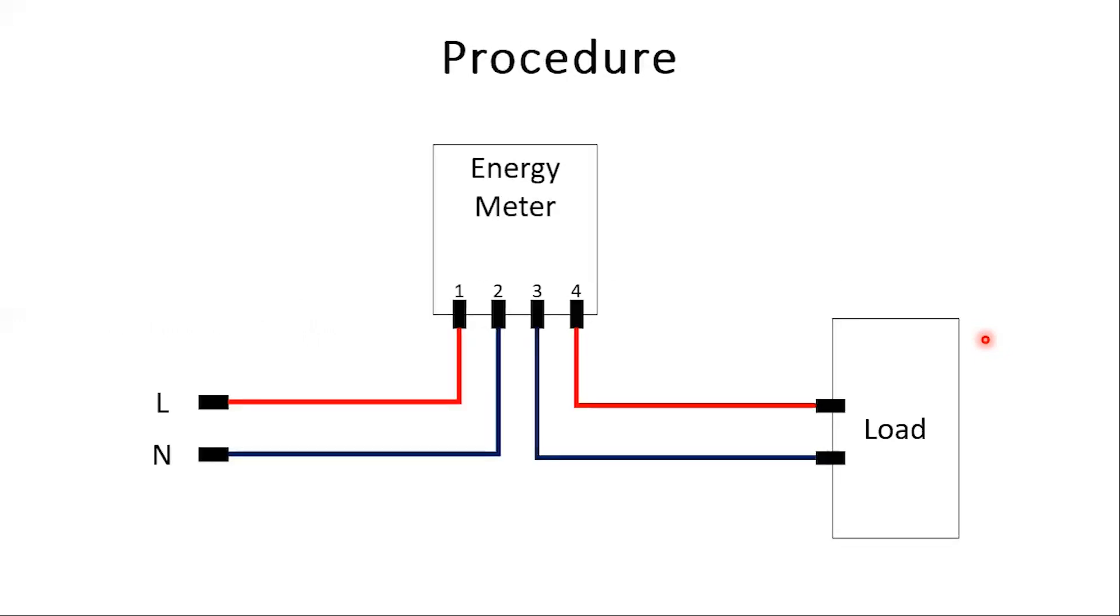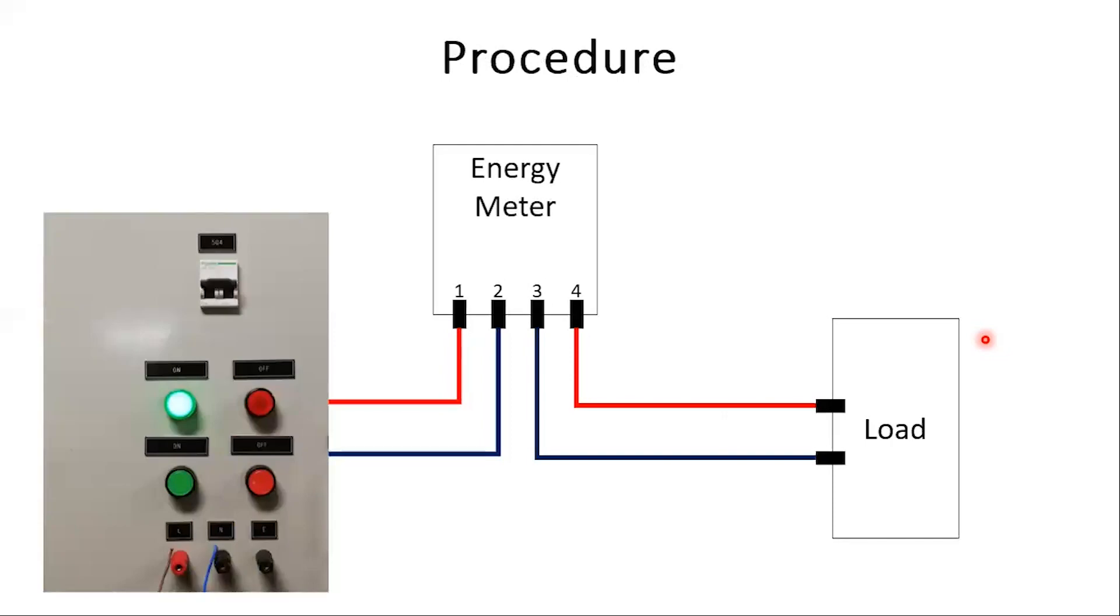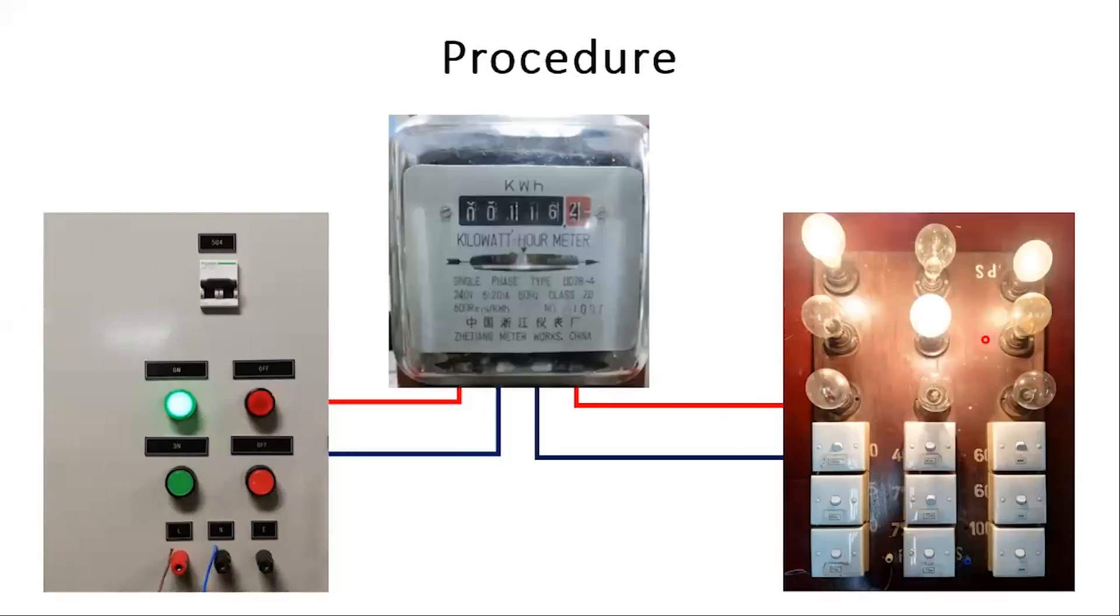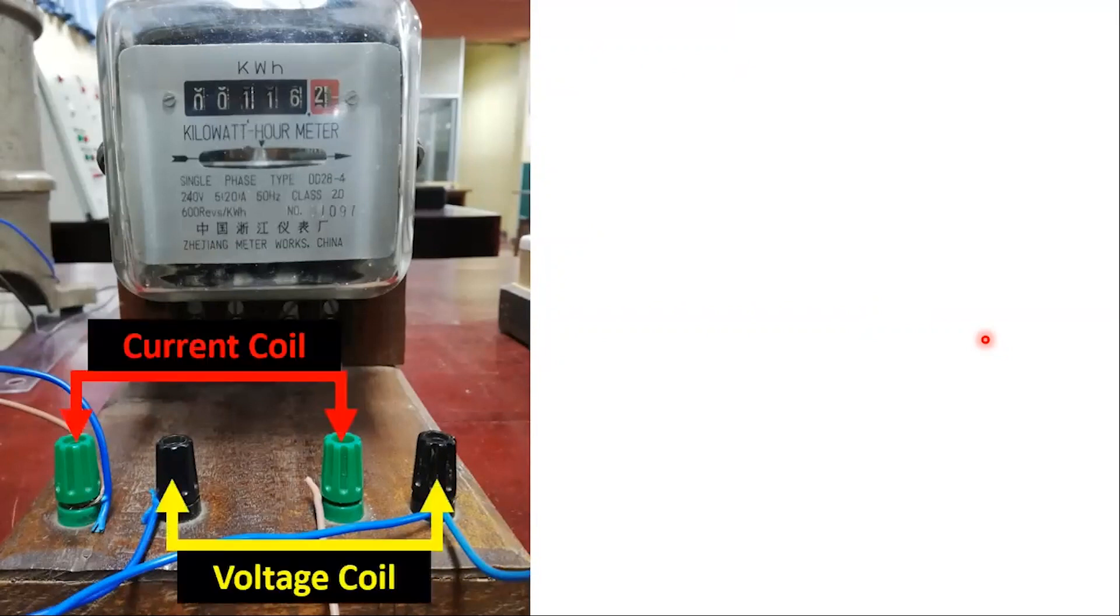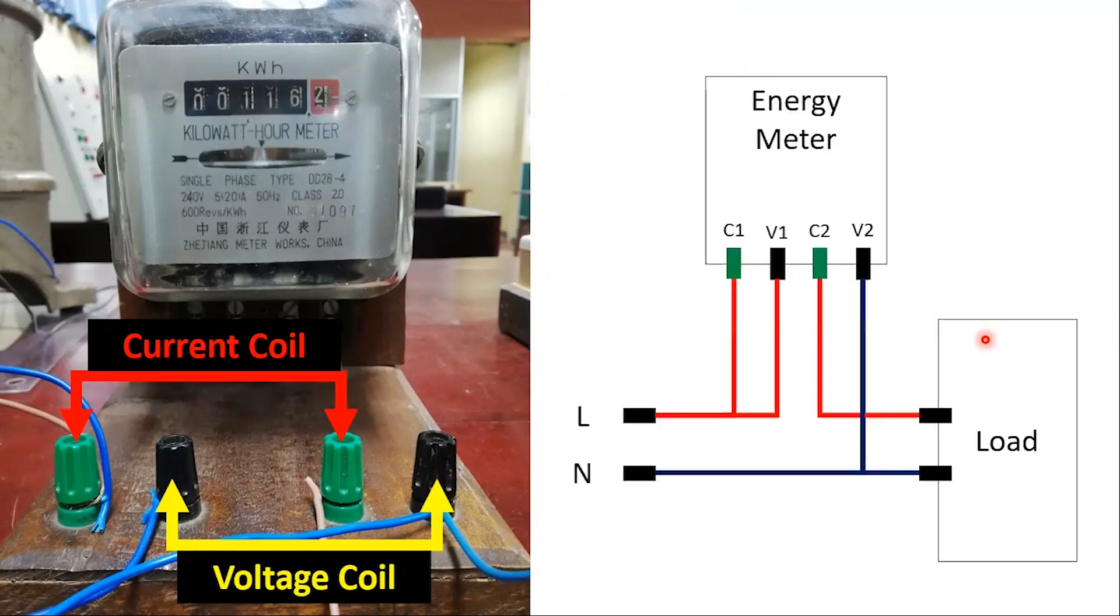Moving on to the procedure, as mentioned before it is a simple setup where we have a single phase supply, the load, and an energy meter. Usually connecting an energy meter is straightforward, but in the meter we use, the terminals are rewired to access the current coil and the voltage coil directly. Hence we must go by the first principles and connect it such that the current coil is in series with the load and the voltage coil is in parallel with the load.